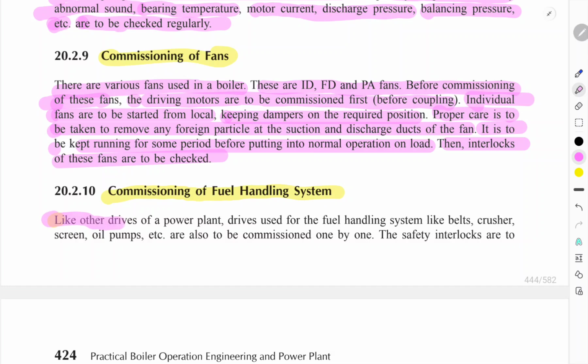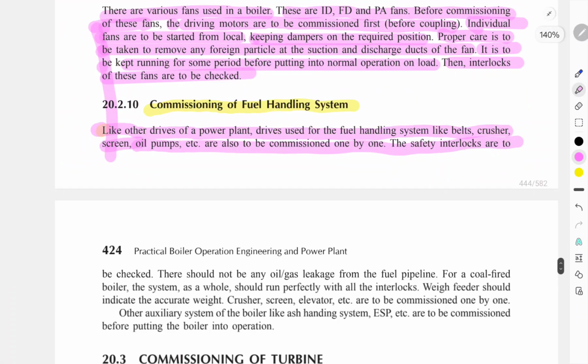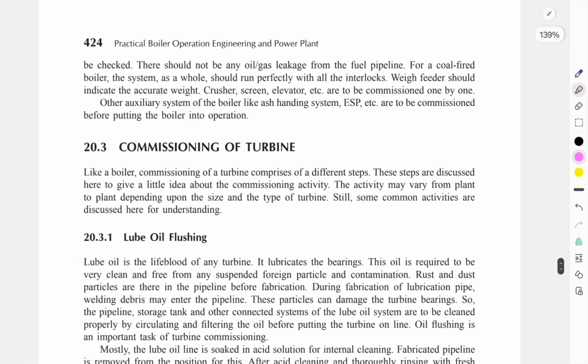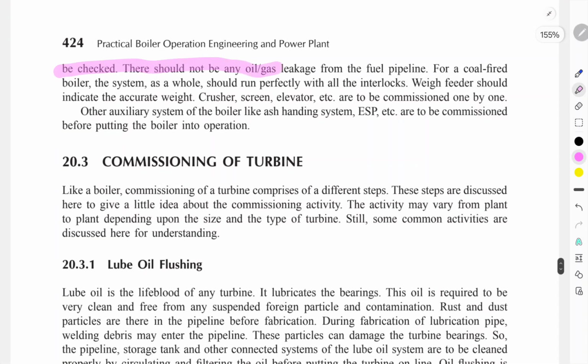Like other drives of power plant, drives used in the fuel handling system are belt, crusher, screen, oil pump, and also the commissioning of safety interlocks. To be checked: there should not be any oil leakage of the fuel line in the coal fired boiler system. The whole system should run perfectly in the interlock. The weigh feeder should indicate accurate weight.